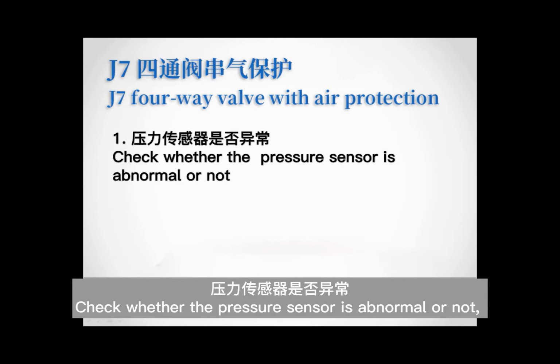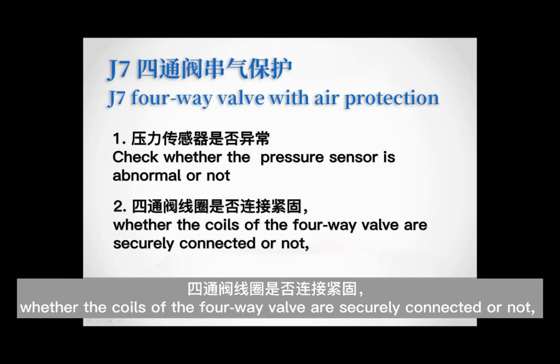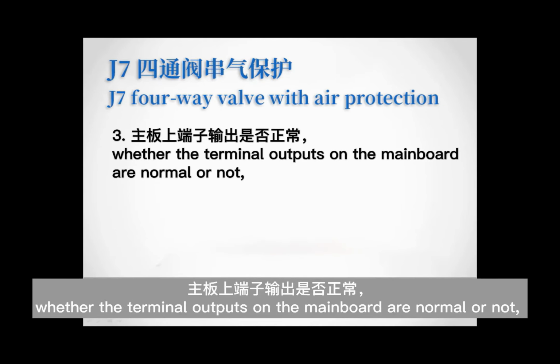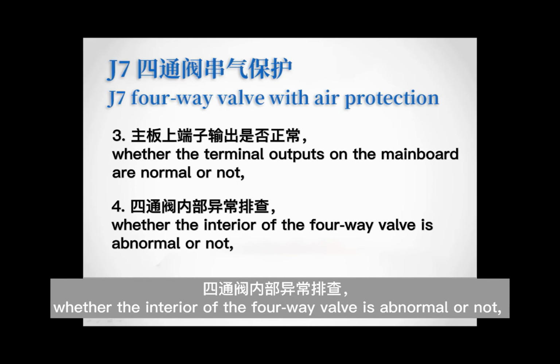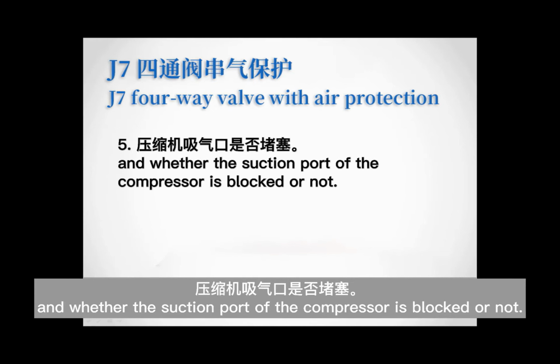Check whether the pressure sensor is abnormal or not, whether the coils of the four-way valve are securely connected or not, whether the terminal outputs on the main board are normal or not, whether the interior of the four-way valve is abnormal or not, and whether the suction port of the compressor is blocked or not.